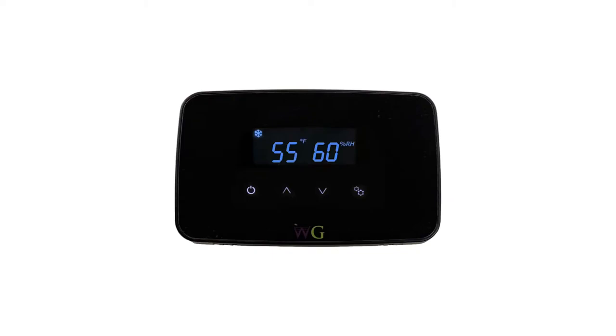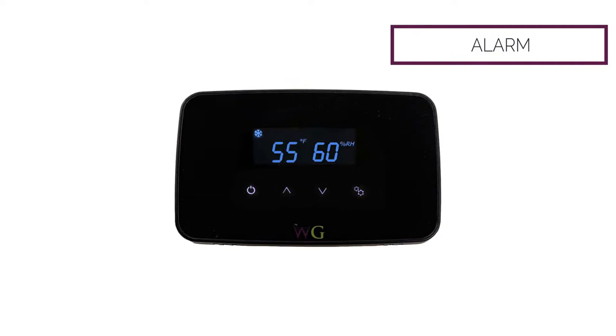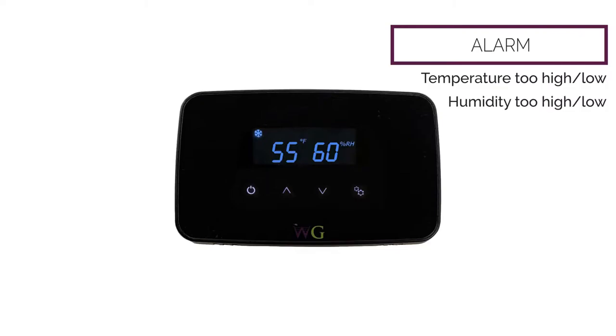Our controls are always going to show you and display the temperature and humidity of the wine space. Okay, it's always going to control temperature, and depending on whether you had a humidifier option or not, it can add moisture back in to control humidity. But it's always going to give you those variables, temperature and relative humidity of the space. So the controls will provide an alarm function as well. So if the temperature is too high in the space or too low in the space, if the humidity is too high or too low, and if there's a fault condition within the refrigeration system, it will alarm at the controls.